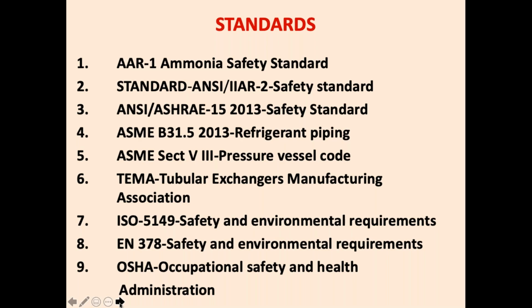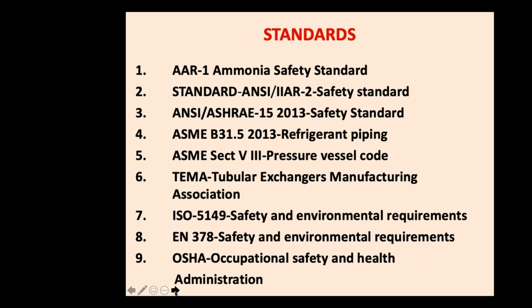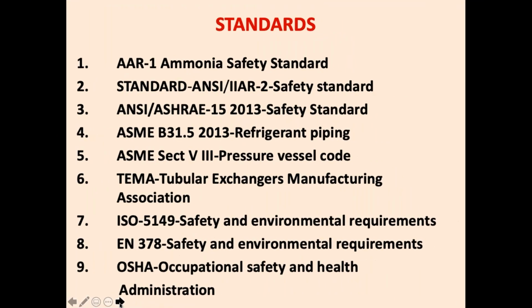Standard ANSI IIAR2, from the International Institute of Ammonia Refrigeration in the USA, approved by the American National Standards Institute, is a safety standard which is available. Then ASHRAE 15 is a safety standard. For piping, ASME B31.5 2013 or the latest, the refrigerant piping code, is a very important standard. Pressure vessel code ASME Section 8 is important. TEMA, the Tubular Exchanger Manufacturers Association standard, is for heat exchanger manufacture like condensers, chillers, etc. ISO 5149 is a safety standard. EN 378 is again a safety standard. And OSHA is the American Occupational Safety and Health Administration standard. This is an important standard.